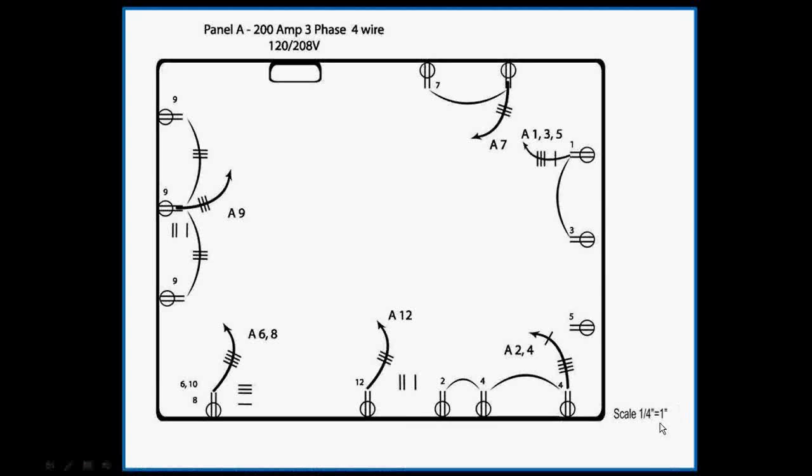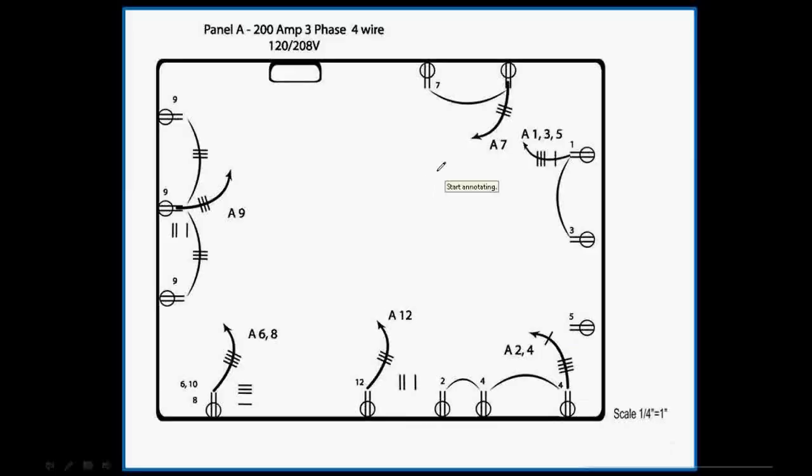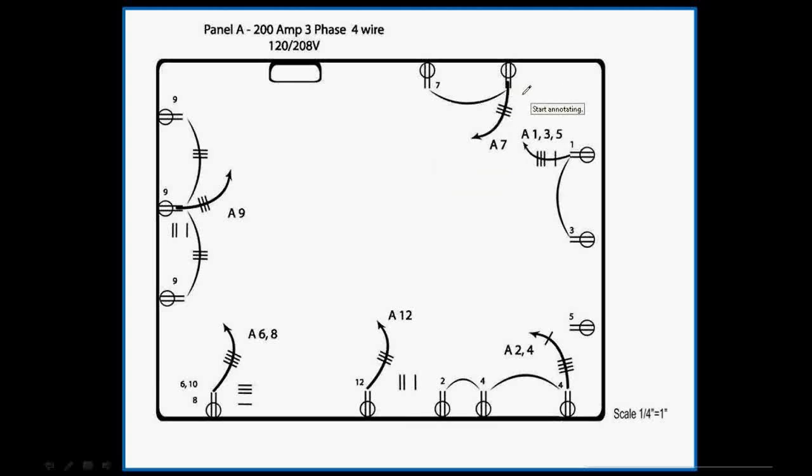Since several conduits on this drawing are the same conduit size and type with the same number of conductors, I can take them off and enter them into Red Rhino in one entry using the Conduit Wizard. I'll take off conduit at right angles to allow enough conduit and wire to go around obstacles or obstructions in the building. I also allow for conduit riser by over-rolling past the end of the conduit run. When you roll past it, the Scalex adds extra length to your count.